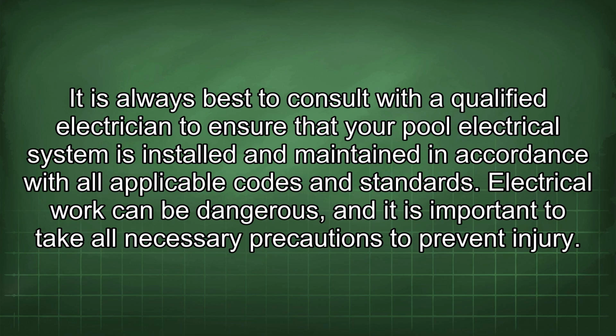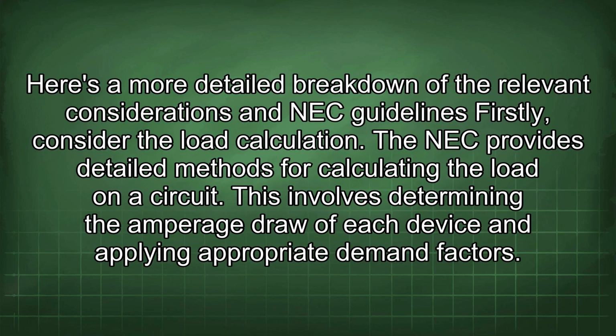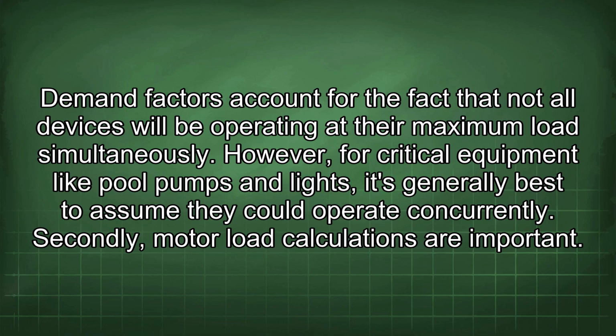Electrical work can be dangerous, and it is important to take all necessary precautions to prevent injury. Here's a more detailed breakdown of the relevant considerations and NEC guidelines. Firstly, consider the load calculation. The NEC provides detailed methods for calculating the load on a circuit. This involves determining the amperage draw of each device and applying appropriate demand factors. Demand factors account for the fact that not all devices will be operating at their maximum load simultaneously.